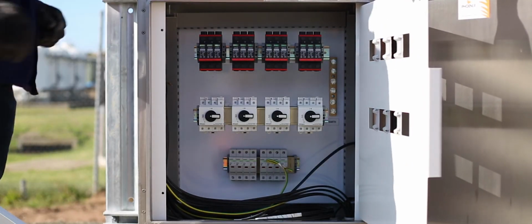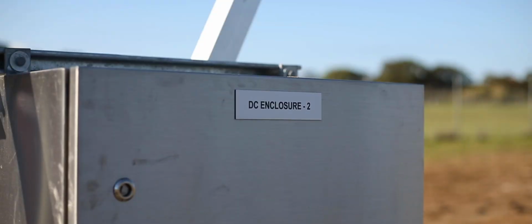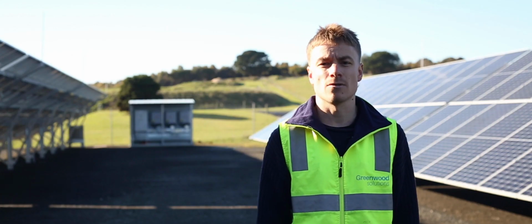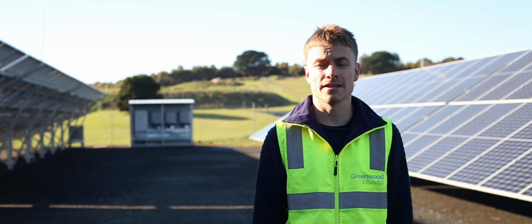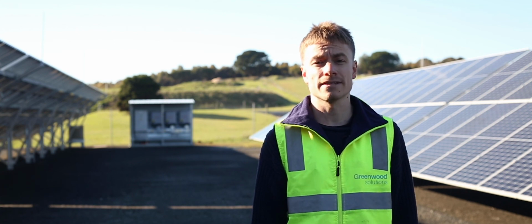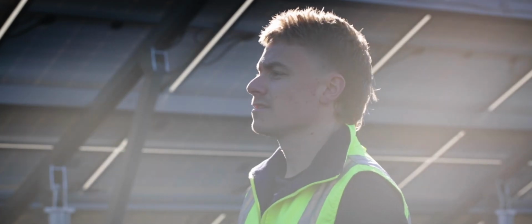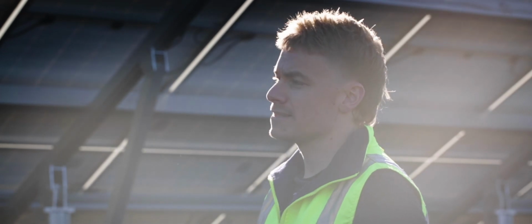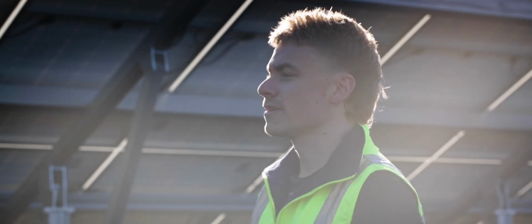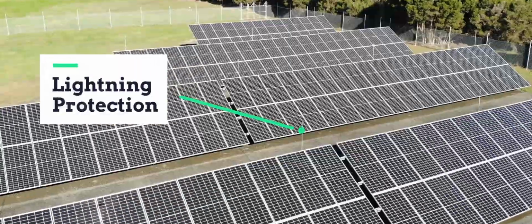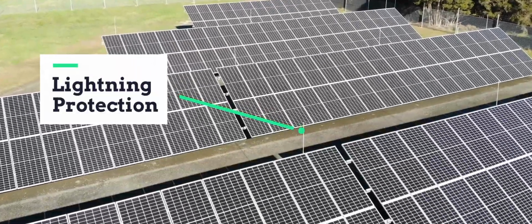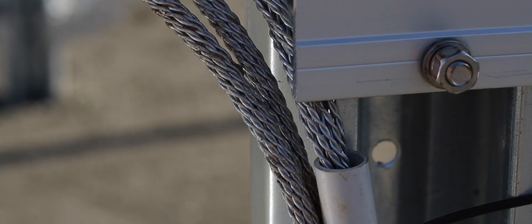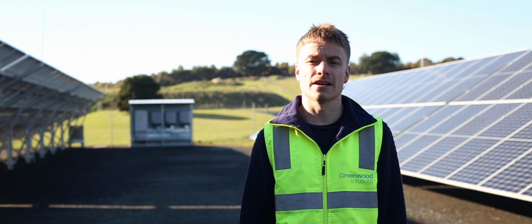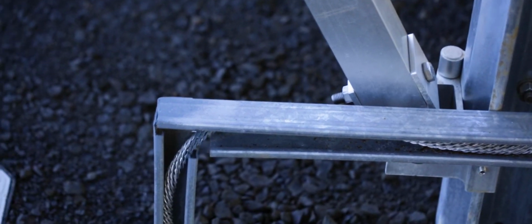There's DC surge protectors in each of the DC combiner boxes. There's 3 of these installed at the array, and then there's also DC surge protection inside the Fronius inverters. There's AC surge protection located in the PVDB and the SCA extension where the protection relay is. The lightning rod's installed at the array to basically stop the panels getting struck by lightning if the area is going to be struck by lightning. It's then linked to a tinned aluminium cable which is then interconnected to earth electrodes underground.